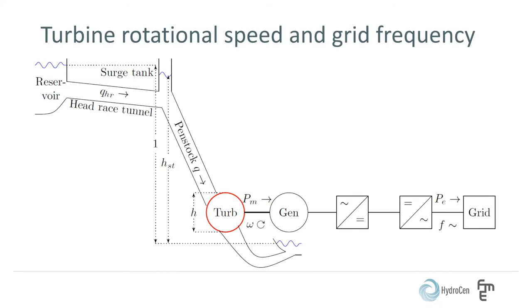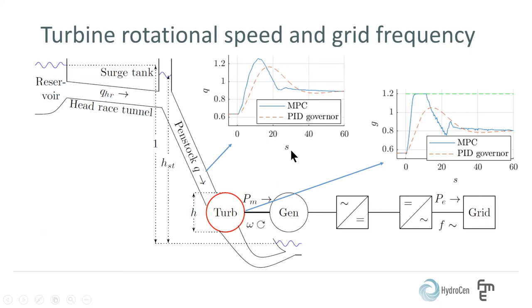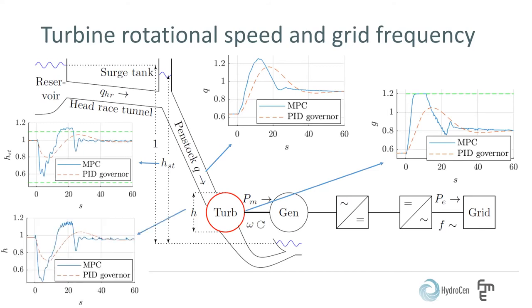The MPC increases the guide vane opening of the turbine and thereby the turbine flow faster than the PID controller. This is possible since the MPC considers the constraints of the hydraulic system, such as the surge tank head and turbine head. The MPC will therefore change the guide vane opening as fast as possible without exceeding these constraints. While the PID controller has to be parametrized conservatively to avoid too high or too low surge tank head causing damage to the system.